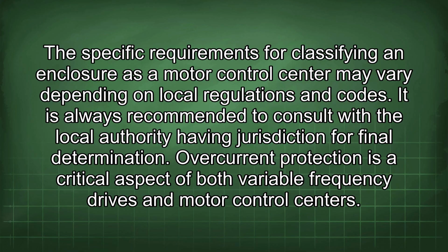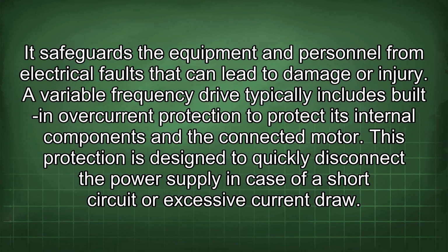Overcurrent protection is a critical aspect of both variable frequency drives and motor control centers. It safeguards the equipment and personnel from electrical faults that can lead to damage or injury. A variable frequency drive typically includes built-in overcurrent protection to protect its internal components and the connected motor. This protection is designed to quickly disconnect the power supply in case of a short circuit or excessive current draw.